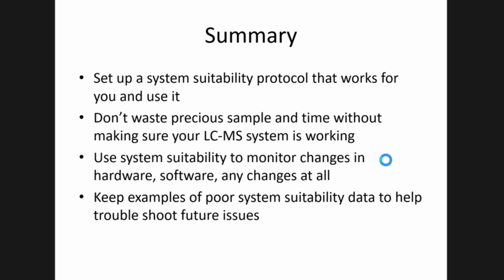Use system suitability to monitor changes over time. This by far has helped me to minimize my instrument downtime, and I've been able to learn things about how to keep it running well without having to call in service to fix something. Keep examples of poor system suitability data to help troubleshoot future issues.